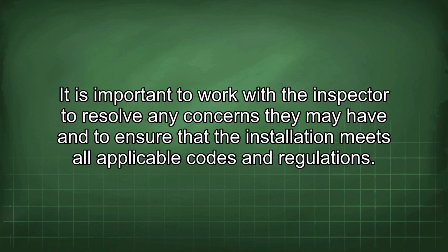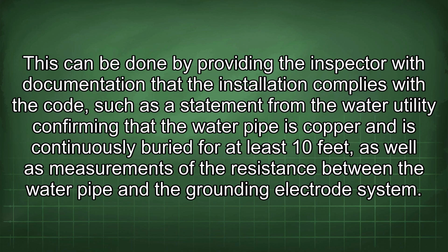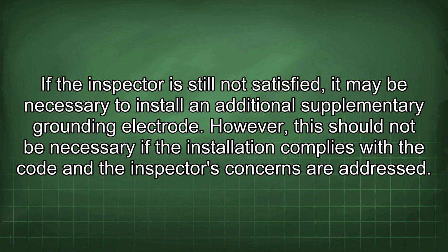It is important to work with the inspector to resolve any concerns they may have and to ensure that the installation meets all applicable codes and regulations. This can be done by providing the inspector with documentation that the installation complies with the code, such as a statement from the water utility confirming that the water pipe is copper and is continuously buried for at least 10 feet, as well as measurements of the resistance between the water pipe and the grounding electrode system. If the inspector is still not satisfied, it may be necessary to install an additional supplementary grounding electrode. However, this should not be necessary if the installation complies with the code and the inspector's concerns are addressed.